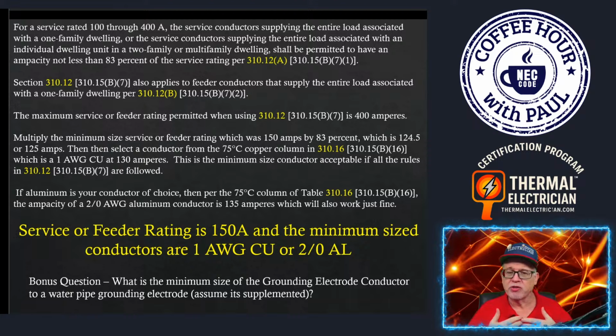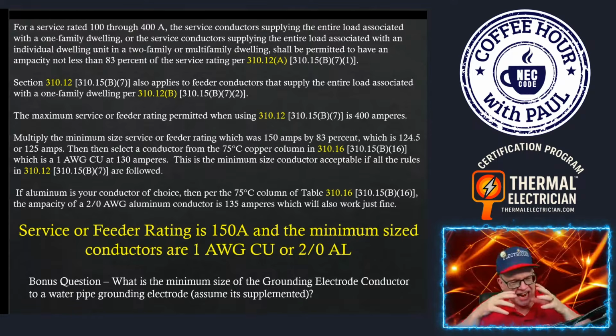That's why it's so important to torque it correctly the first time, because if you don't damage it, then that termination will stay consistent. Okay. It's not Paul preaching to you. It's facts. I've spent a career working with wiring cable, understanding the nuances of the conductor and the molecular structure and how it reacts to being compressed and how creep works and that type of thing.